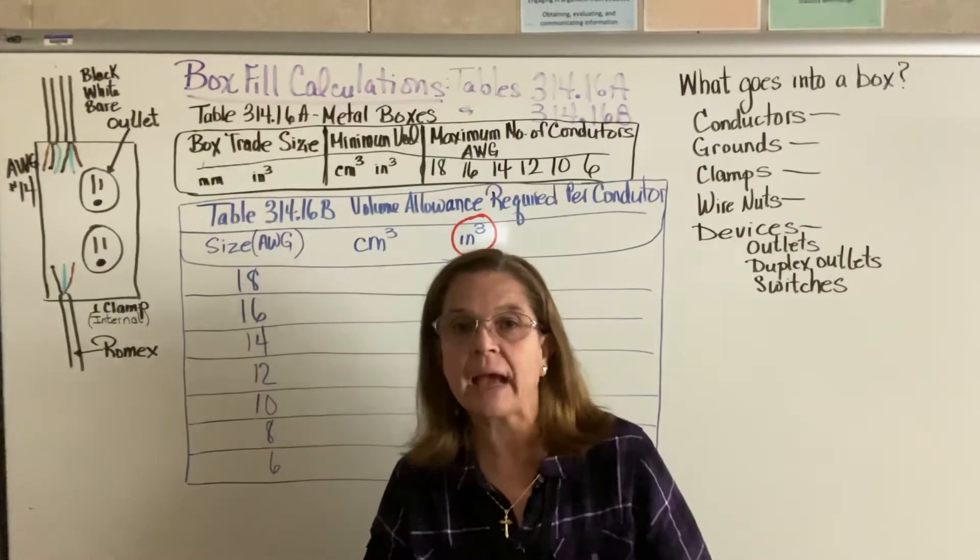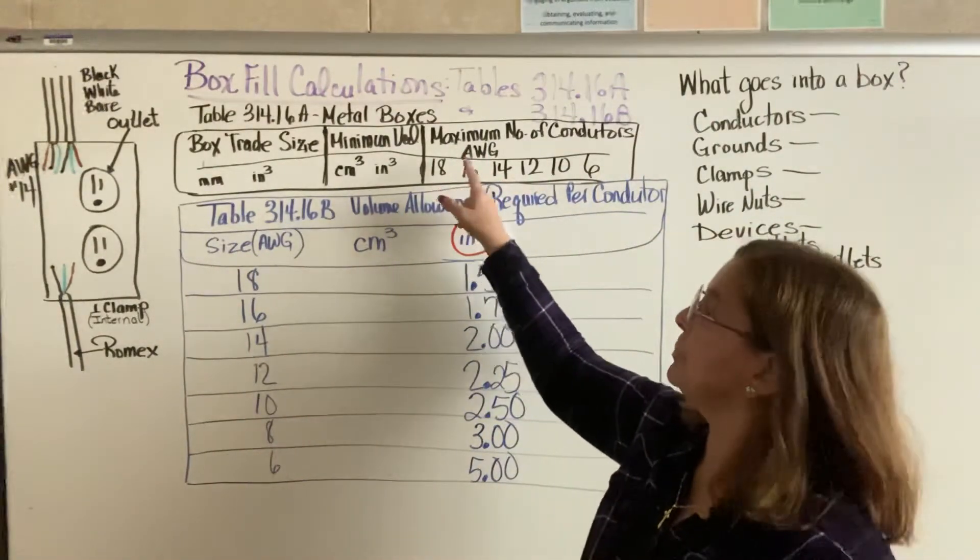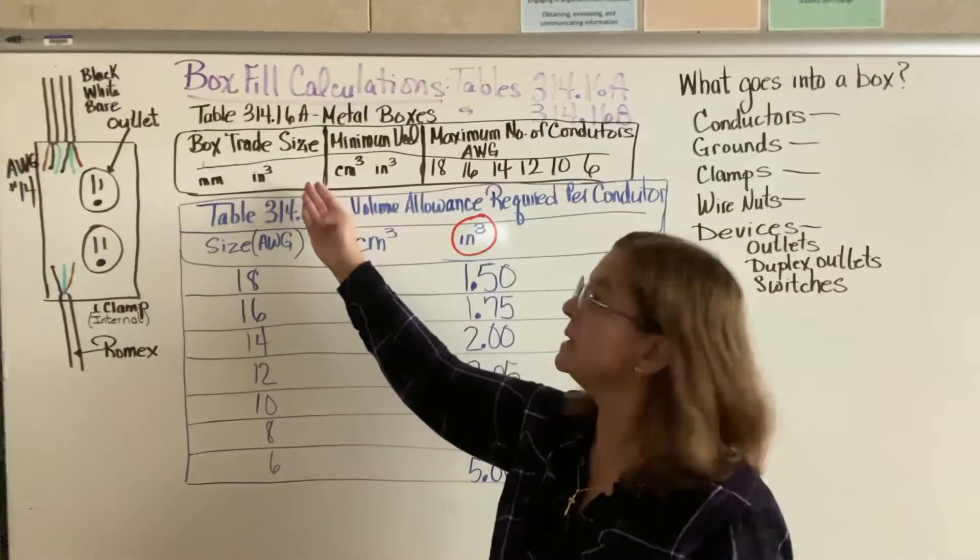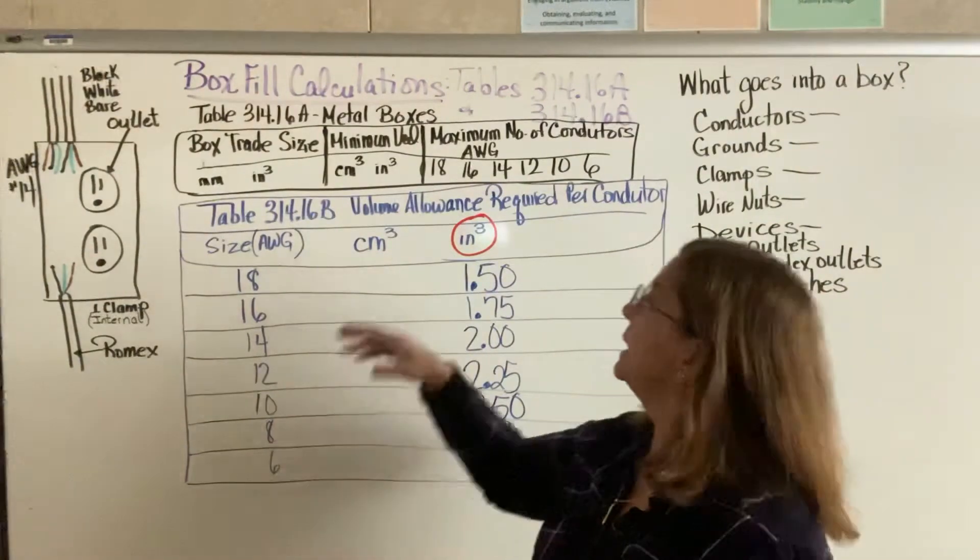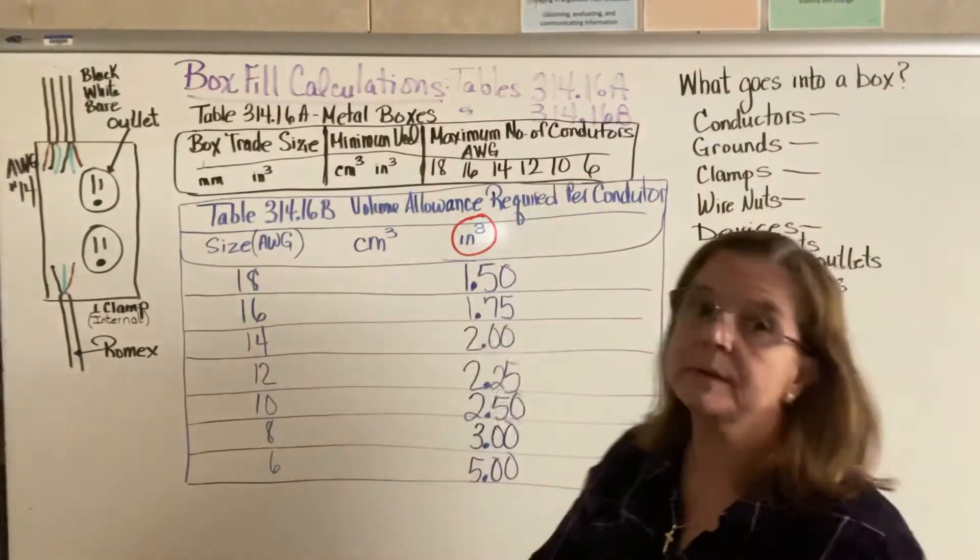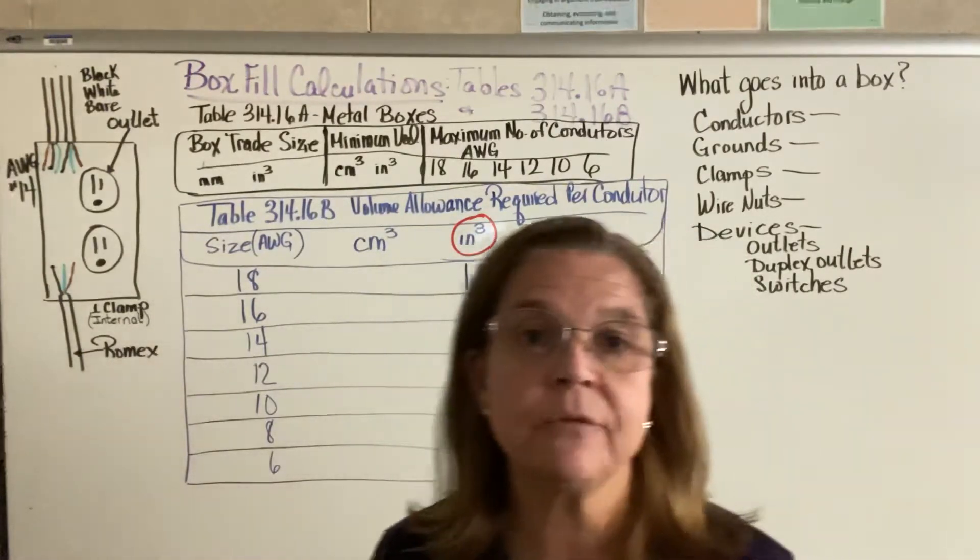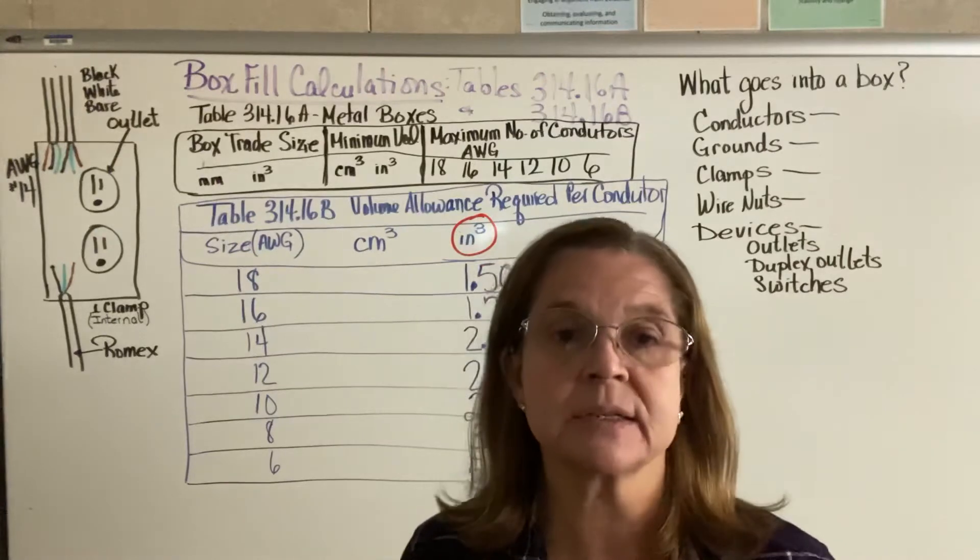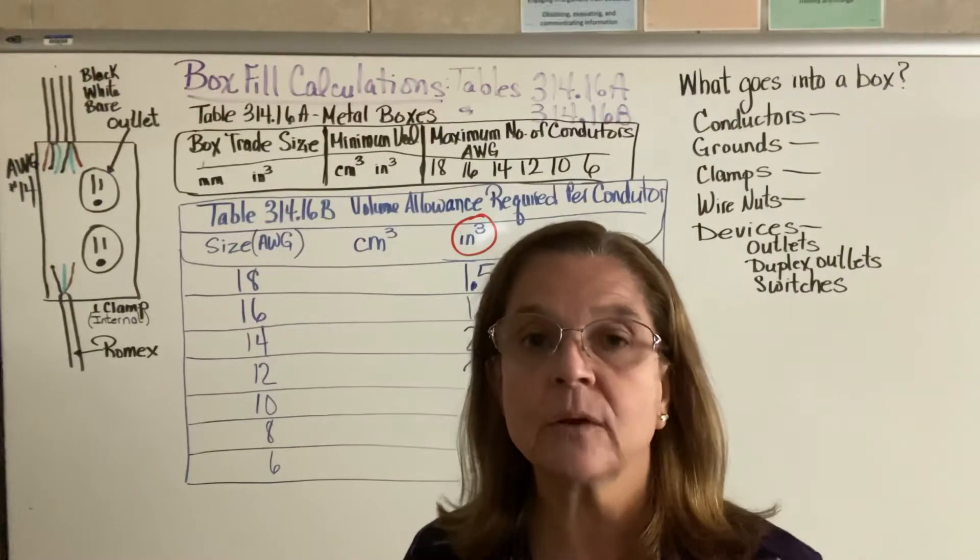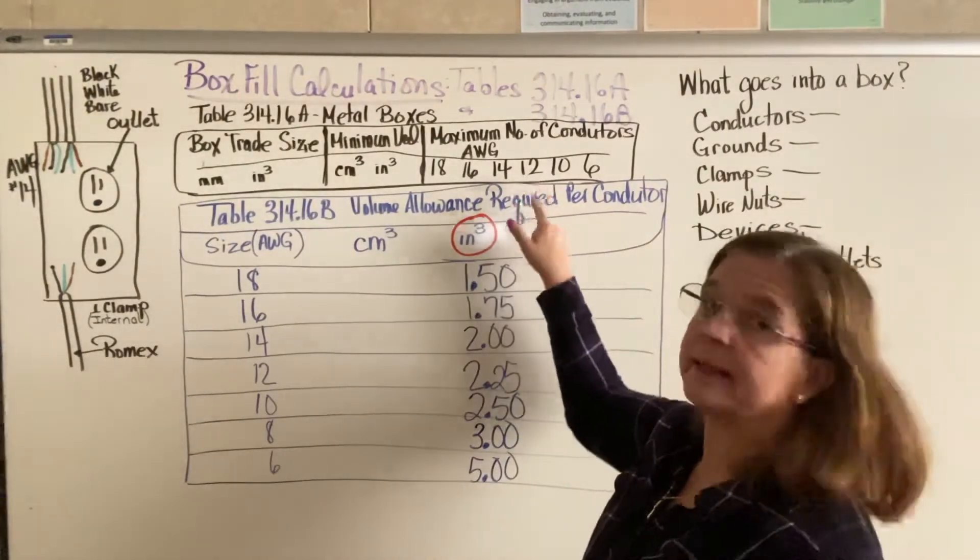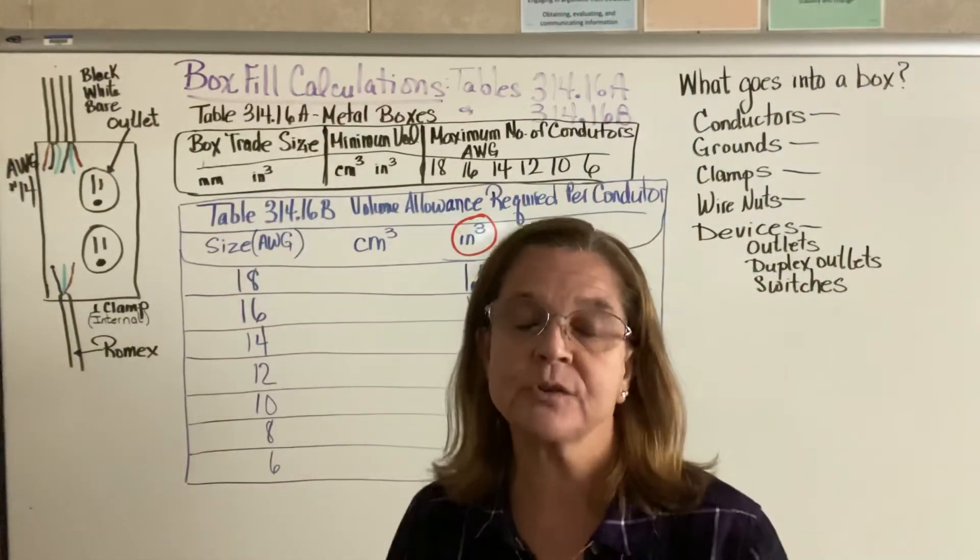I put the outline for 314.16A on top here. Basically, you'll see the box trade size, the minimum volume allowed, and the maximum number of conductors. You would use that if you're using all number 12 conductors. You're using four number 12 conductors, you would go down, find number 12, find the number four, and then read to the left to see what size box you need.